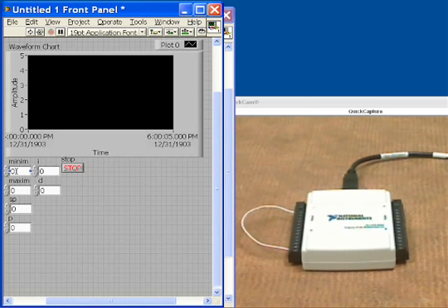The one thing that I do want to set, my minimum is 0 and that's fine, but I want my maximum value to go up to 5. So that's going to limit what my PID can set as ranges or values. Next we want to go and set the PID values, and we'll set them at some numbers. We'll choose 0.1 for P, we'll set it 0.1 for I, and then 0.01 for D. And those are numbers I just derived by knowing a little bit about this setup.